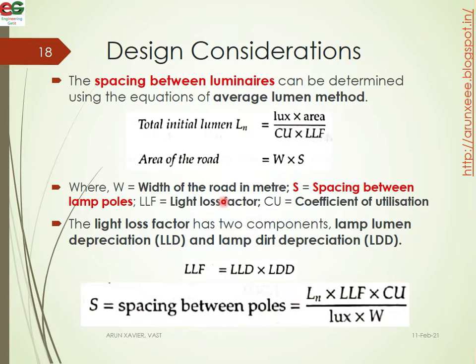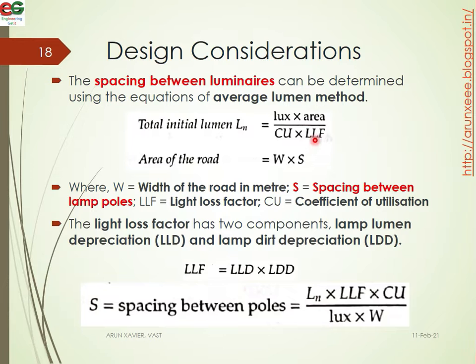For design considerations, the first parameter is the spacing between two luminaires. The spacing between luminaires can be determined using the average lumen method: total lumens equals lux times area divided by CU times LLF. The area equals W times S, where W is the width of the road and S is the spacing between the two lamp poles. Rearranging, S equals LN times LLF times CU divided by lux times W.